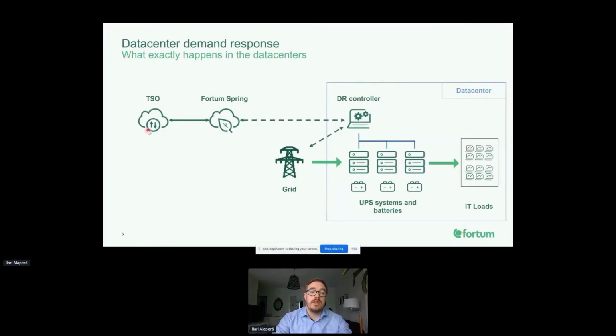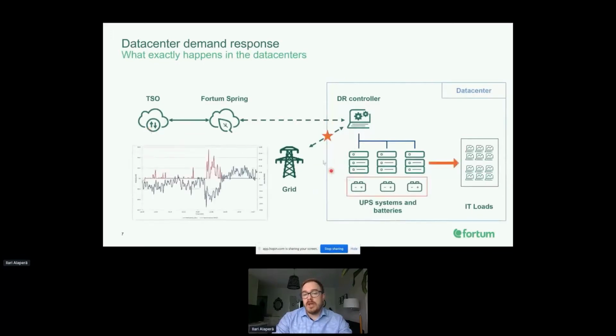We sell the capacity to the TSOs, and if there's an event - if grid frequency deviates - we get notified from the grid measurements, and the UPS systems are activated, drawing energy momentarily from their batteries, giving a very nice response to that frequency deviation. The IT loads of the data centers are not impacted at all. We're mainly pushing data centers for the FFR market, which requires a very fast response but also a very limited response.